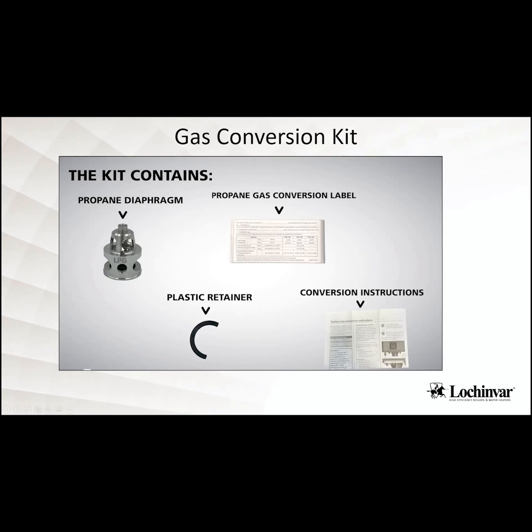So you have this diaphragm that's here, this plastic retainer. When you put the new diaphragm in there, that plastic retainer just goes around it and holds it on there as you put the gas manifold back on. This conversion label just lets anyone know that that unit has been converted to propane. And then there are those conversion instructions that are in there. Converting it to propane is pretty easy. You just pull that manifold off the front, you switch out that diaphragm and put it back on. And then there's some programming that I'll show you here in just a minute. But any questions on that gas conversion kit?